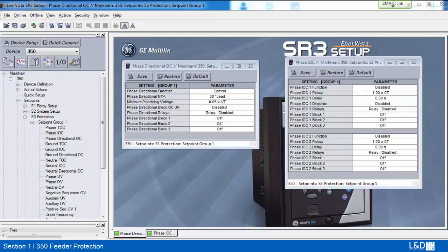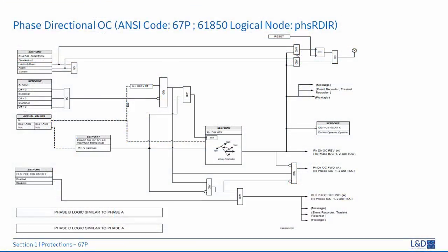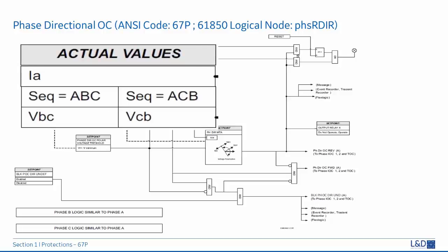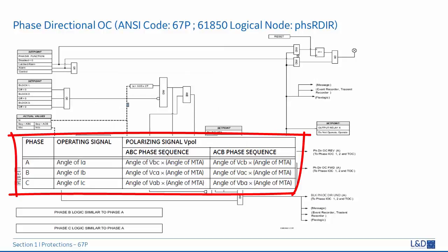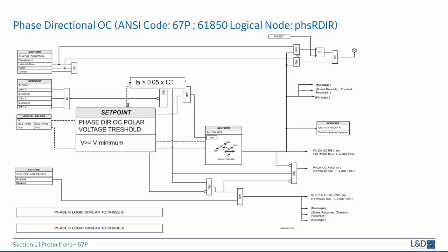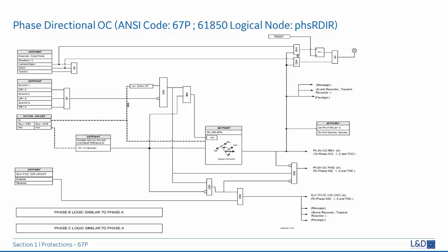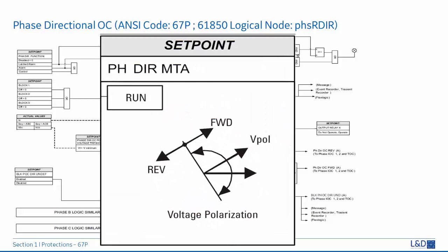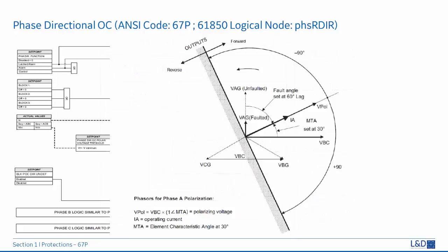From the logic diagram, phase A current needs VBC as polarizing voltage for ABC rotation. For phase B and C, voltages VCA and VAB are used for polarizing. The phase directional function will be inhibited when operating current is less than 5% of CT or polarizing voltage is less than the minimum voltage level.